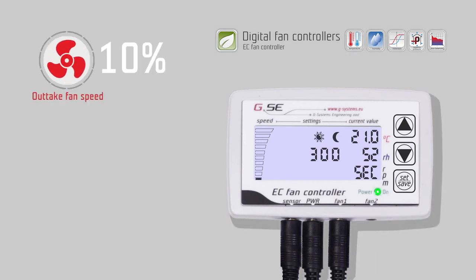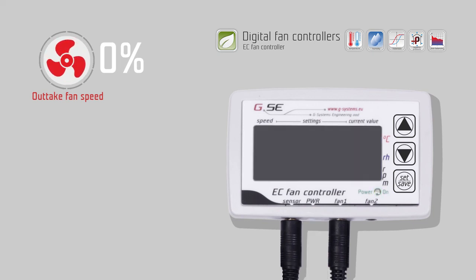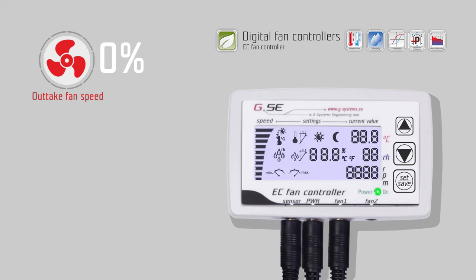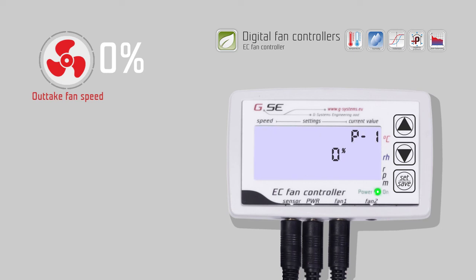Not every EC fan has the same minimum speed. This can be easily corrected with the EC fan controller. Disconnect the power supply cable from the controller. Wait a few seconds. Press and hold the up button, and then connect the power supply again. Keep holding the button for more than 3 seconds.